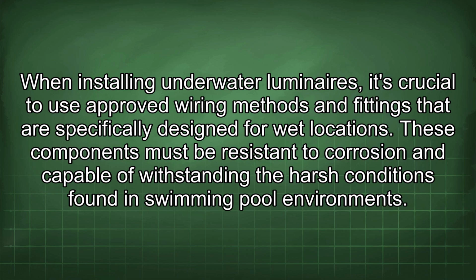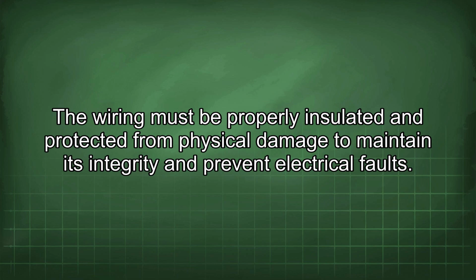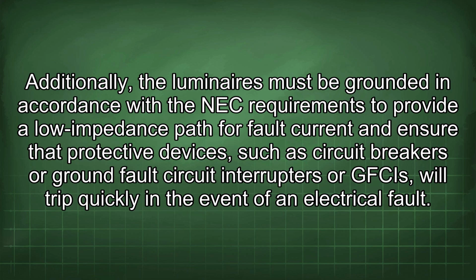When installing underwater luminaires, it's crucial to use approved wiring methods and fittings that are specifically designed for wet locations. These components must be resistant to corrosion and capable of withstanding the harsh conditions found in swimming pool environments. The wiring must be properly insulated and protected from physical damage to maintain its integrity and prevent electrical faults. Additionally, the luminaires must be grounded in accordance with the NEC requirements to provide a low-impedance path for fault current and ensure that protective devices, such as circuit breakers or ground fault circuit interrupters, or GFCIs, will trip quickly in the event of an electrical fault.